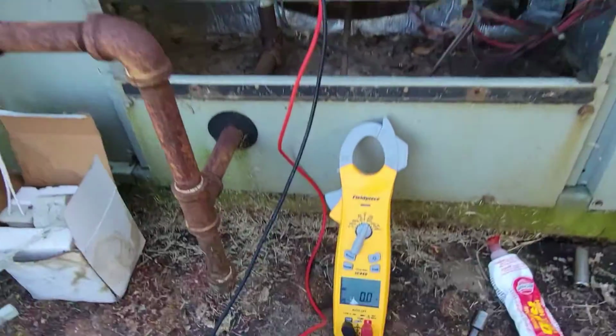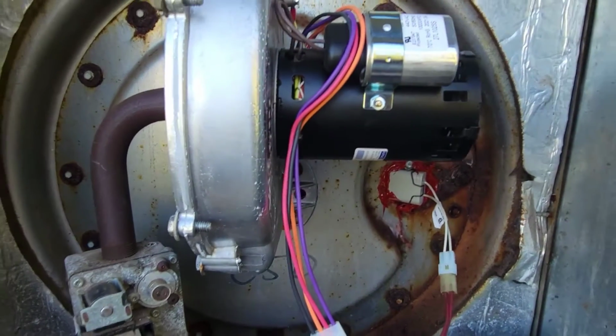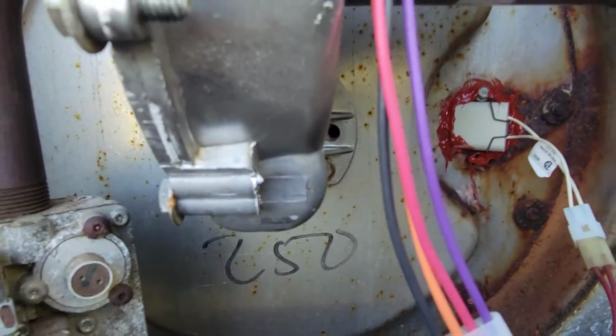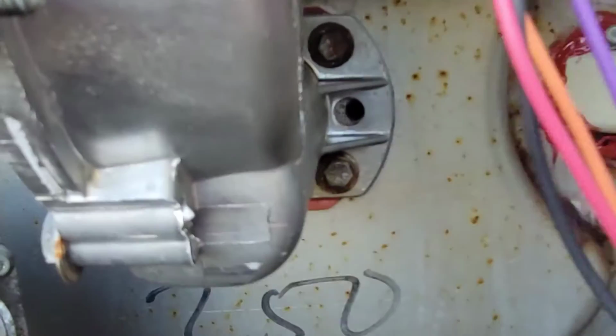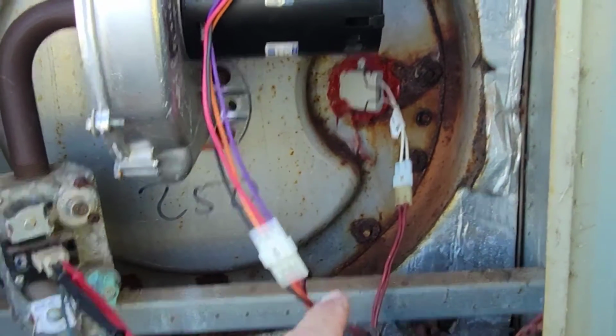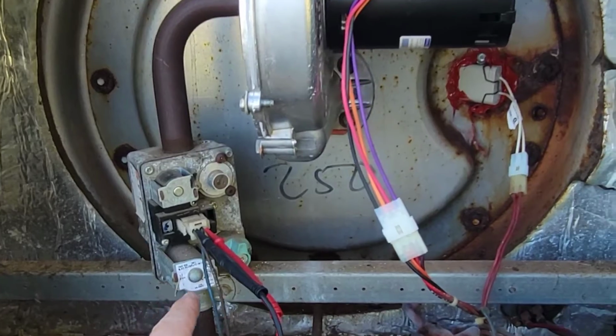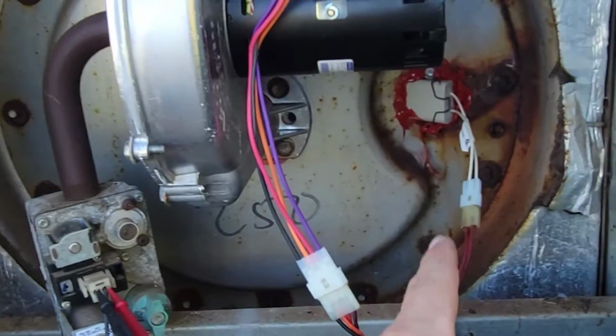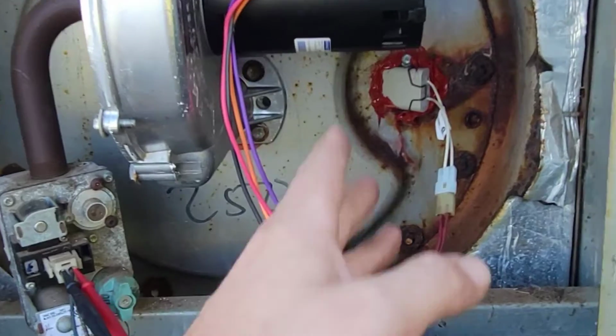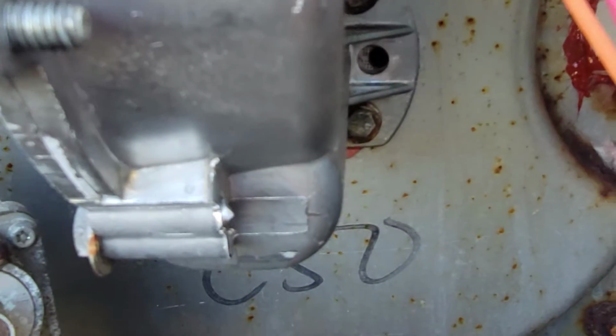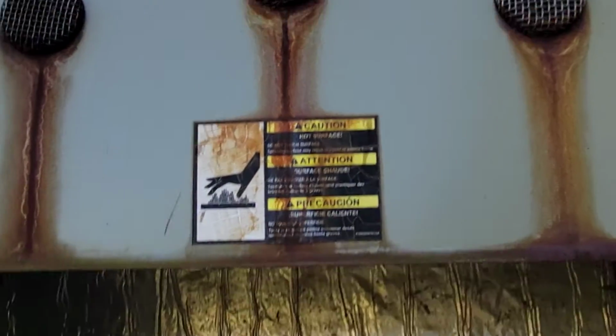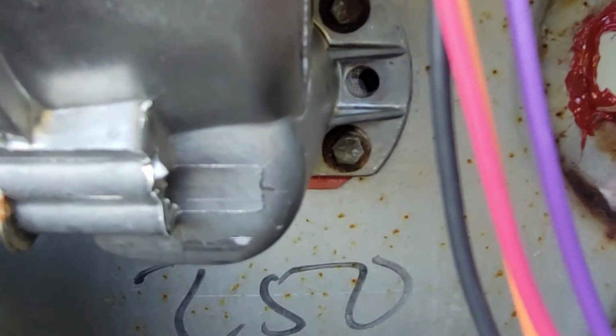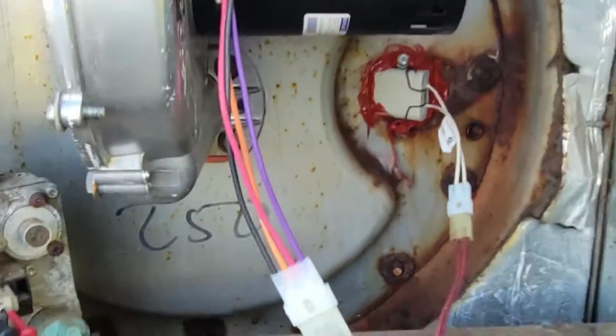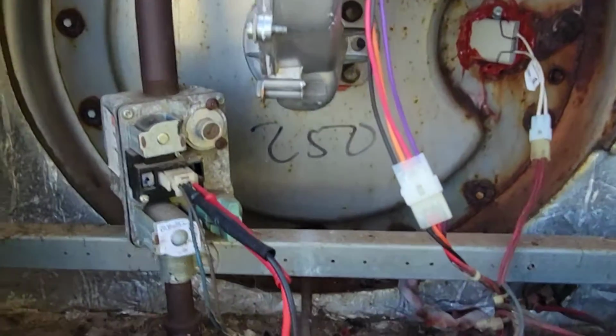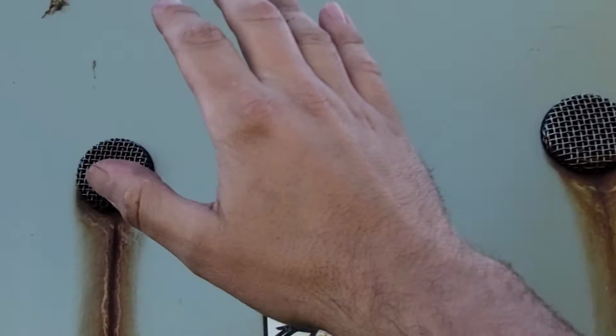Keep that in mind. So right now we've got the inducer motor running. We should see some glow once we have power to our hot surface igniter, because that's what happens before the gas valve gets its power. You have inducer motor, safeties, hot surface igniter, and then gas valve. Oh man, we got a lot of rust blow out of there. So, couldn't really see the glow, but it's definitely working because it's lit.